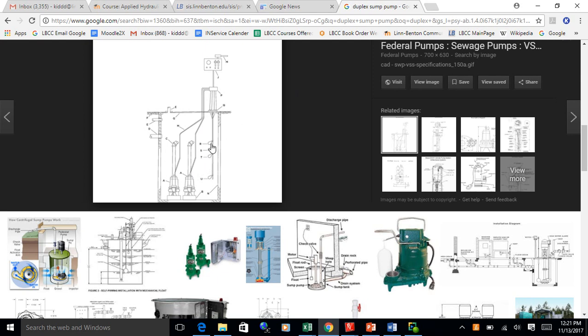Now what do you suppose switch number 3 up here is for? Alarm. Yeah. Public works, which I wouldn't call it public works. I would substitute the pronoun me for that for most of you guys. Because if both pumps can't keep up, you've got an alarm switch up here too. And if the water keeps rising, you're going to get a signal somewhere that says Houston, you have a problem, and you've got to get out there and try and do something about it. And probably a roaring rainstorm or something like that is probably how that's going to go.